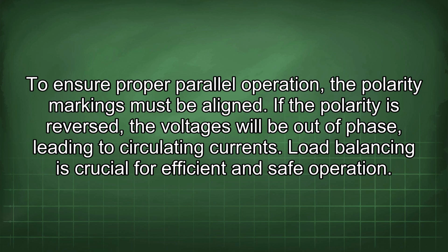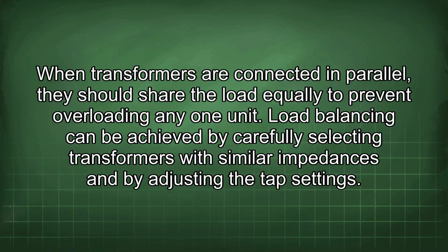If the polarity is reversed, the voltages will be out of phase, leading to circulating currents. Load balancing is crucial for efficient and safe operation. When transformers are connected in parallel, they should share the load equally to prevent overloading any one unit. Load balancing can be achieved by carefully selecting transformers with similar impedances and by adjusting the tap settings.